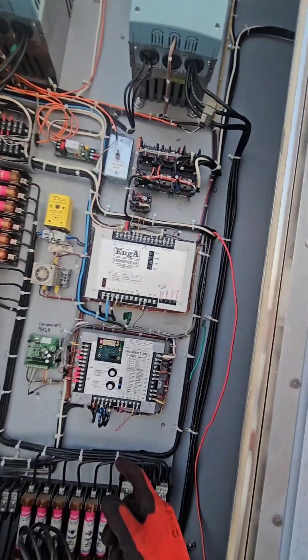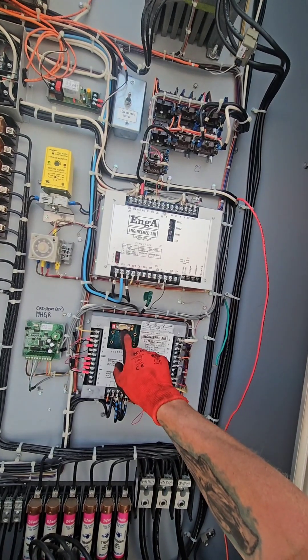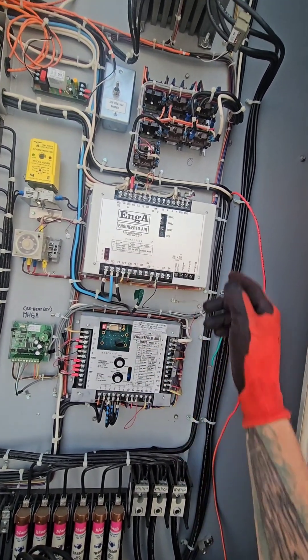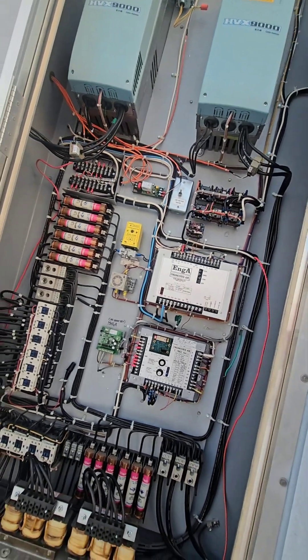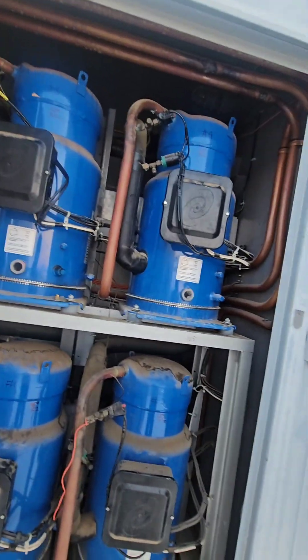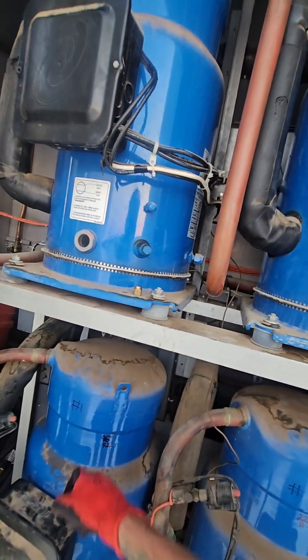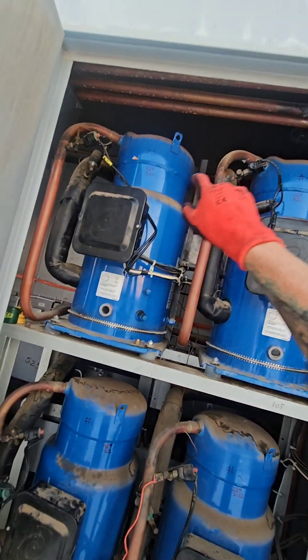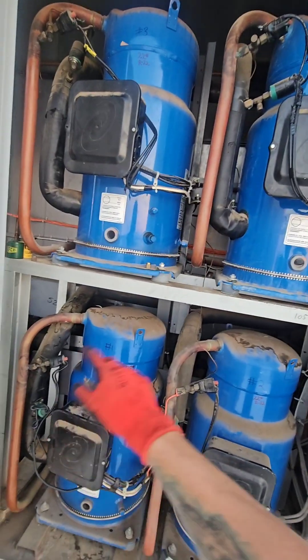They were nice enough to give me the program so I can use my laptop, which I'm going to do - log on to this unit and see what I can see in there. Haven't checked it out yet. This particular one has 96 pounds on the first stage. These are all independent circuits - they aren't tandems or anything.